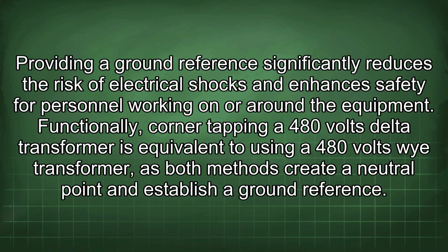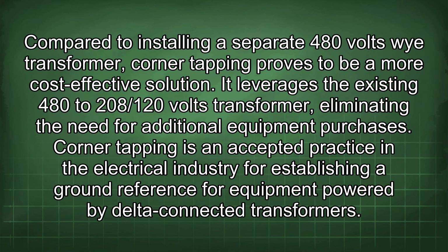Providing a ground reference significantly reduces the risk of electrical shocks and enhances safety for personnel working on or around the equipment. Functionally, corner tapping a 480-volt delta transformer is equivalent to using a 480-volt Y transformer, as both methods create a neutral point and establish a ground reference. Compared to installing a separate 480-volt Y transformer, corner tapping proves to be a more cost-effective solution. It leverages the existing 480 to 208/120 volts transformer, eliminating the need for additional equipment purchases.